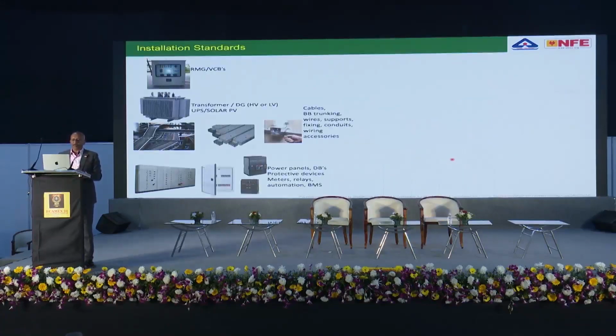First of all, for electrical products, you have so many product standards. For each and every product, there is a product standard, such as wires, plugs and sockets, or your MCBs, MCCBs, RCBOs, motors, cable trays, trunking. There are product standards. And who is responsible for this product standard? Product standard is the headache of the manufacturer of that product. He has to design, he has to provide the product which conforms to the standard. Means he has to make it, he has to test it, and he has to supply the goods in the market, and he has to comply with the standard.